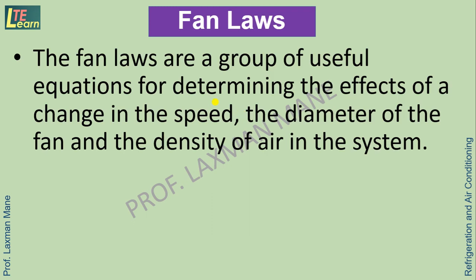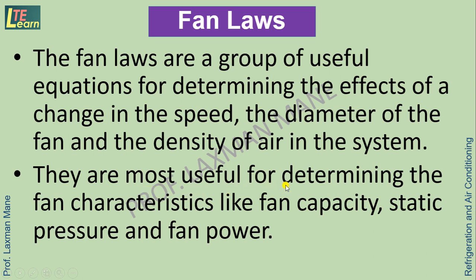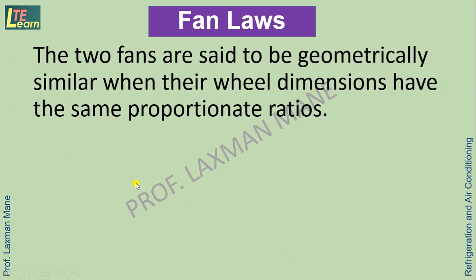Fan laws. The fan laws are a group of useful equations for determining the effects of a change in the speed, the diameter of the fan and the density of air in the system. They are most useful for determining the fan characteristics like fan capacity, static pressure and fan power. Two fans are said to be geometrically similar when their wheel dimensions have the same proportionate ratios.